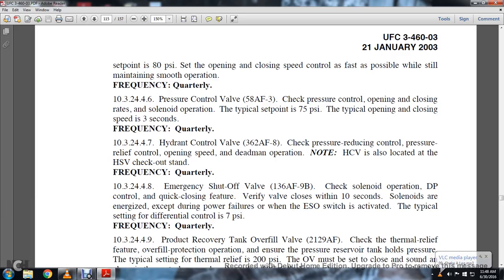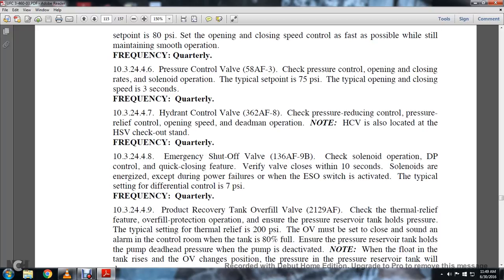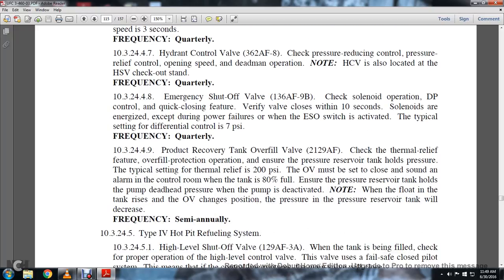Emergency shutoff valve, the 136AF9B model: check solenoid operation, DP control, and quick closing feature, verifying the valve closes within 10 seconds. The solenoids are energized, except during power failures or when the ESO switch is activated. The typical setting of the differential control is 7 psi. That inspection is done quarterly.